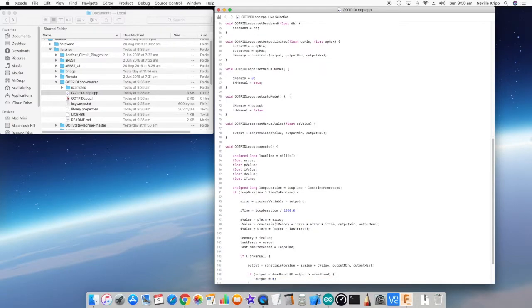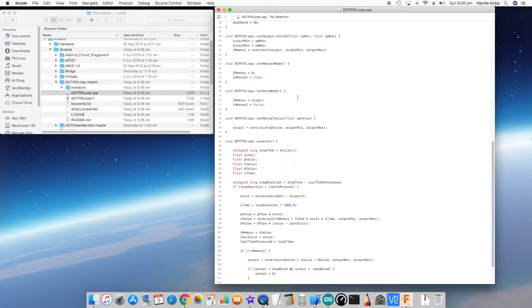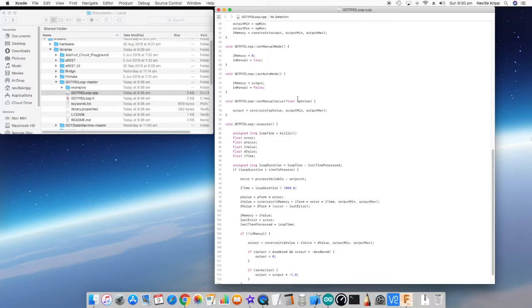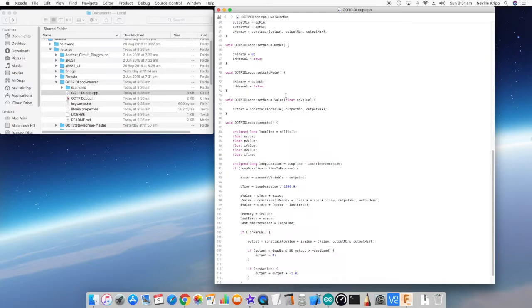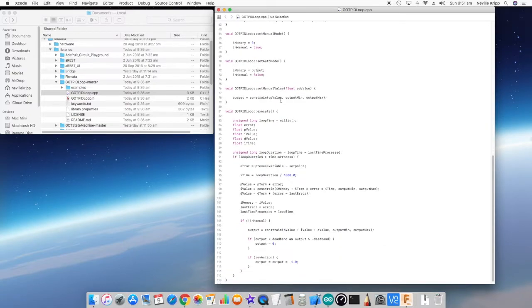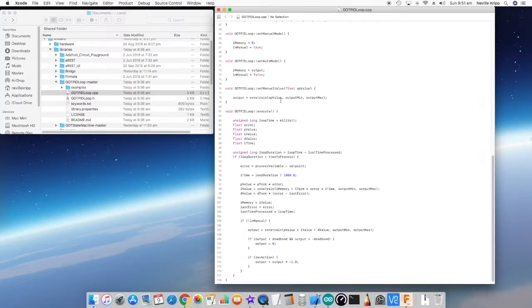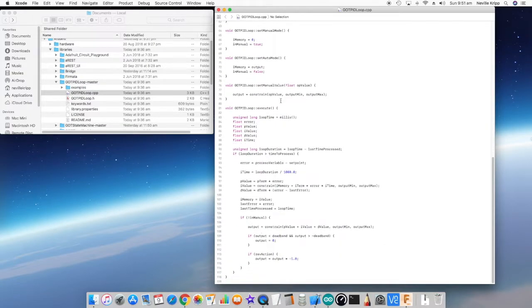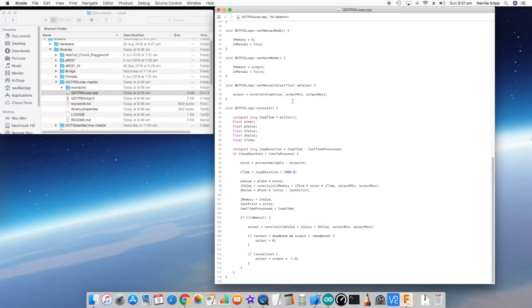We then have a couple of functions to set manual mode and set auto mode, which again are just adjusting internal variables. When it's in auto, we actually load whatever the output is being set to at the moment into i memory, so it effectively gives a bumpless transfer between manual to auto. Next, we have a set manual value, so we just pass a value through and the output is actually set to that value. However, it is constrained within output min and max.